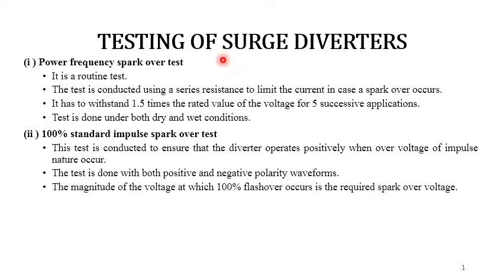Next one we have testing of surge diverters. In modern practice, surge arresters or lightning arresters are the most reliable devices to protect the power system against transient voltages due to lightning and switching surges. They are used from a low voltage of around 400 volts to the highest system transmission voltage, above 765 kV as well. Hence, testing in a precise way, and standardization in the laboratory with standard test procedures, are of great importance in modern power system engineering.